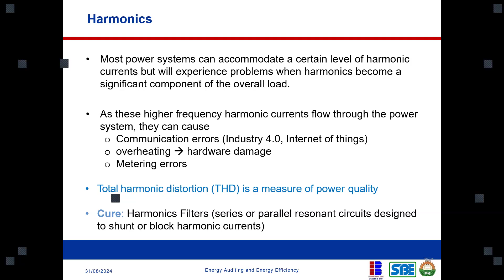These harmonic distortions can be corrected and cured using harmonic filters, which are series or parallel resonant circuits designed to shunt or block those harmonic currents. Electrical engineers can clearly understand how to prevent or correct harmonics, but for general knowledge, just know that to correct harmonic distortion, you use harmonic filters to do that.